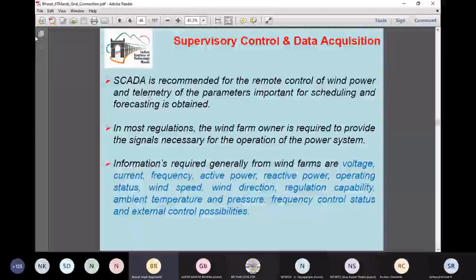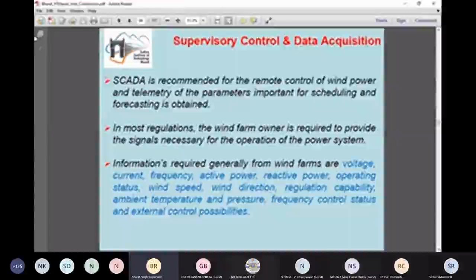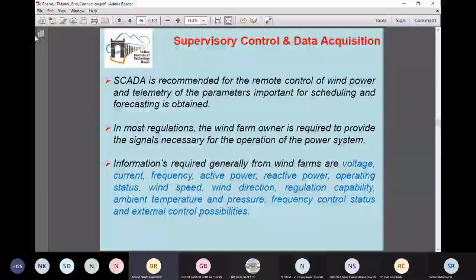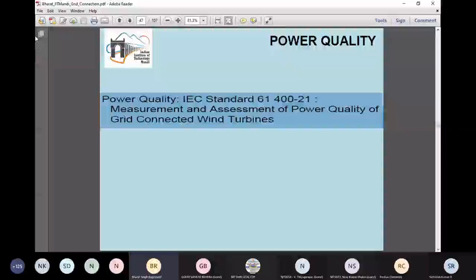Then supervisory control and data acquisition systems should also be installed, with information, parameter values and controllability available for different parameters, as well as different control options. Such remote connections and control possibilities should always be available. This also comes under the grid connection requirements. Next slide is about the power quality standard. The IEC standard needs to be followed for power quality. Power quality broadly covers voltage sag, voltage swell, harmonics and flicker. All of these should also be as per the IEC standard. Next slide, please.